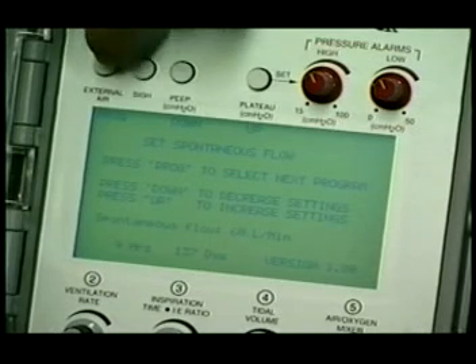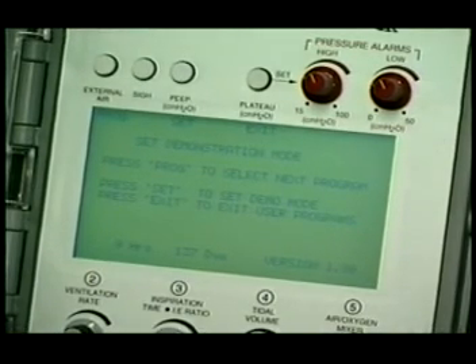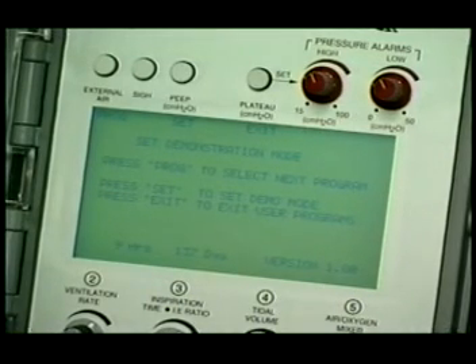The next menu allows us to operate in a demonstration mode for user training. It is interactive, and the only functions that are rendered inoperable are the transducer pressure sensor and the disconnect alarm. On-screen waveforms are simulated. A ventilator circuit may be used, but is not necessary. Do not use a test lung with the demo mode. The last menu allows us to test the backup ventilator. A failure of the primary CPU would cause the backup ventilator to operate. This menu feature allows us to verify its functionality.